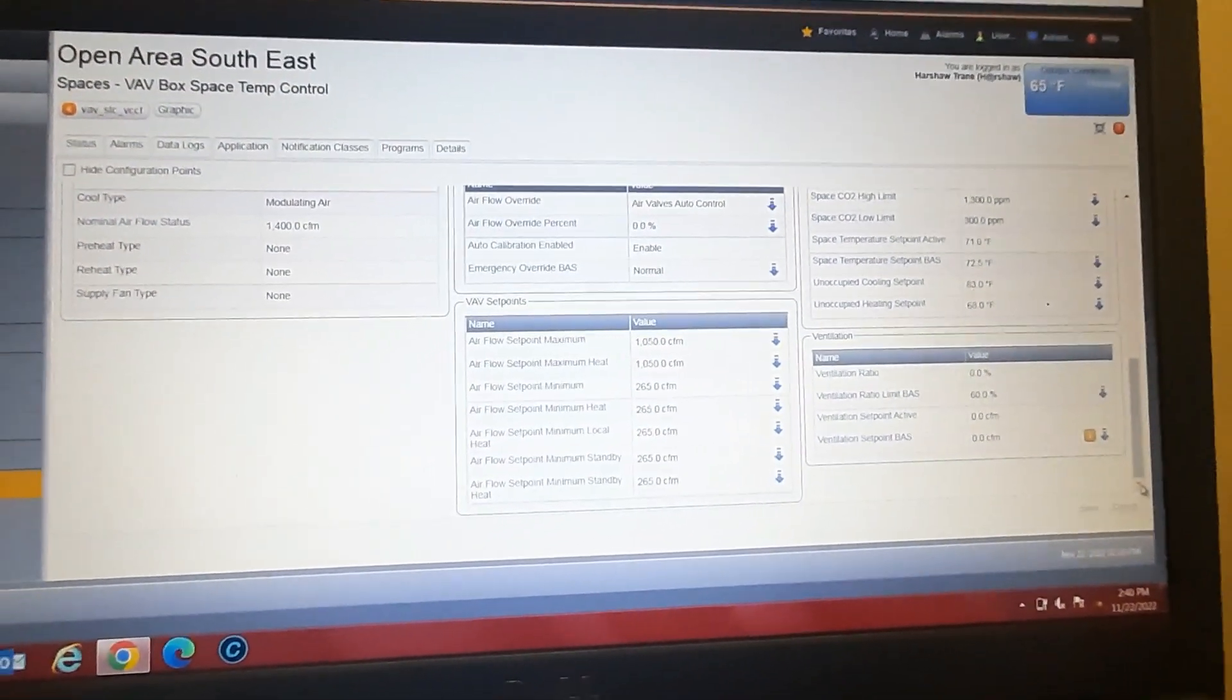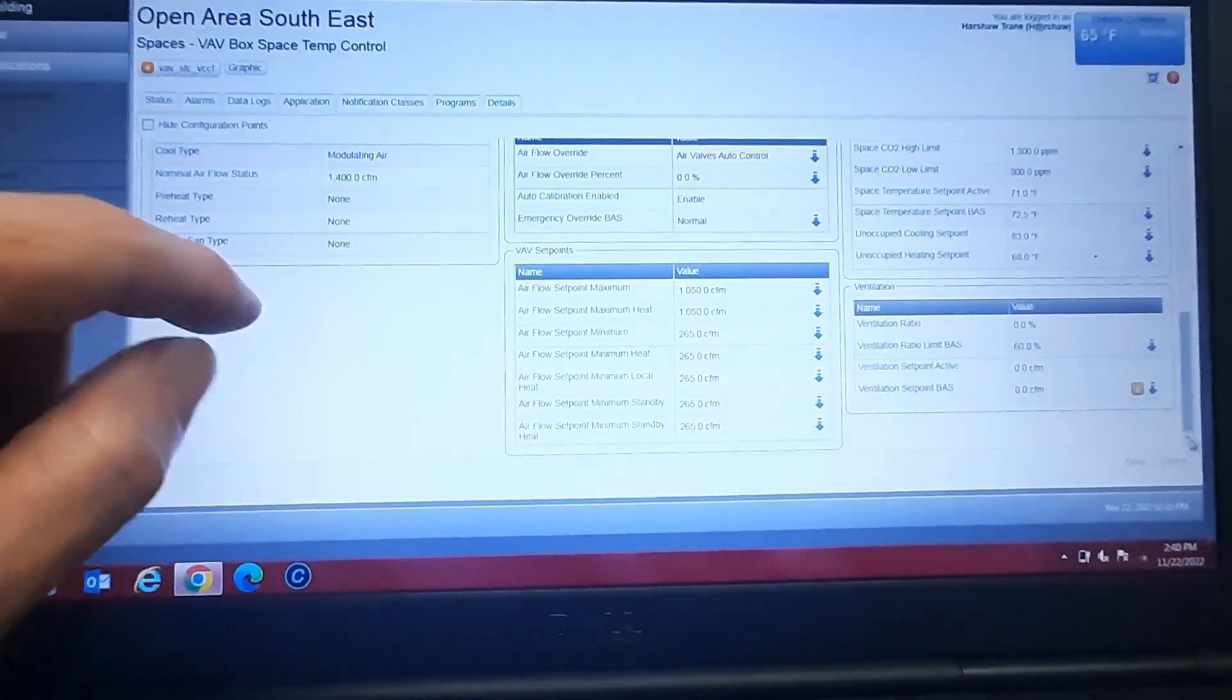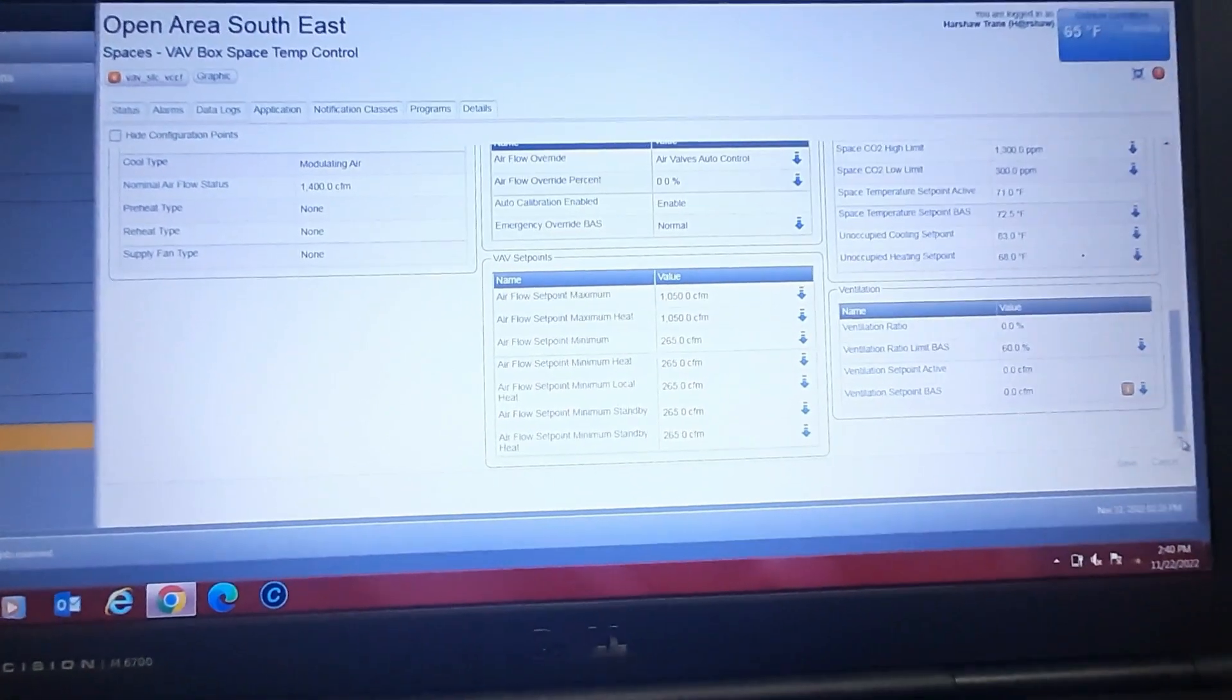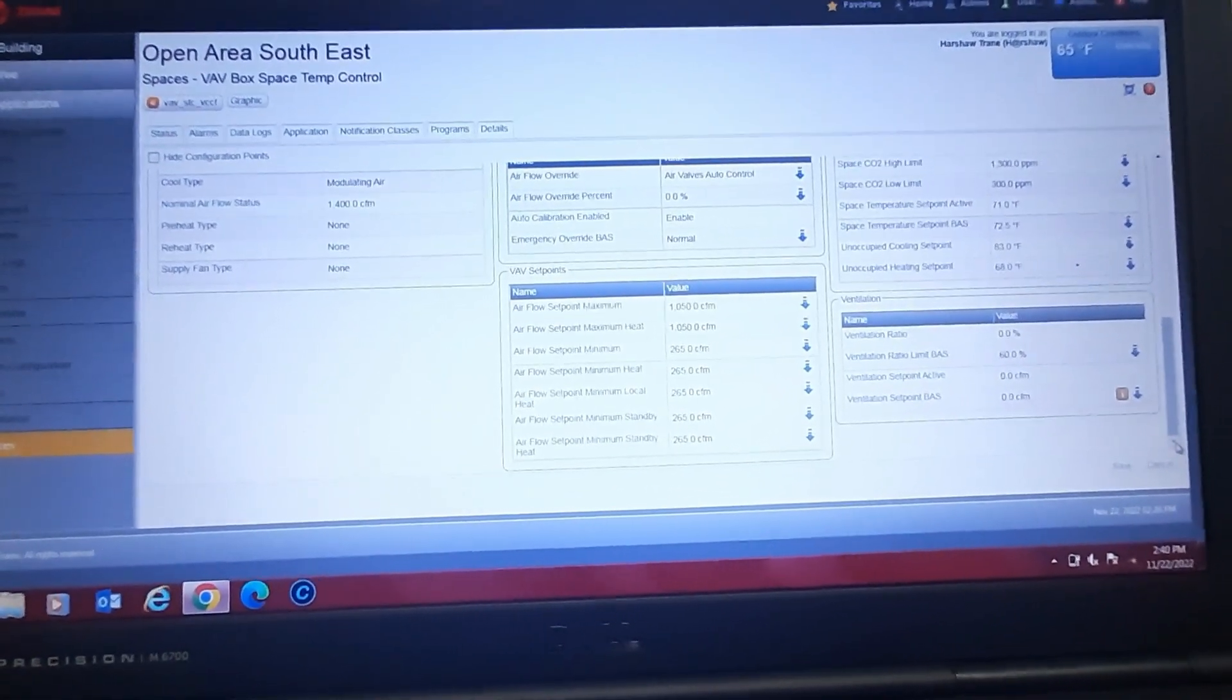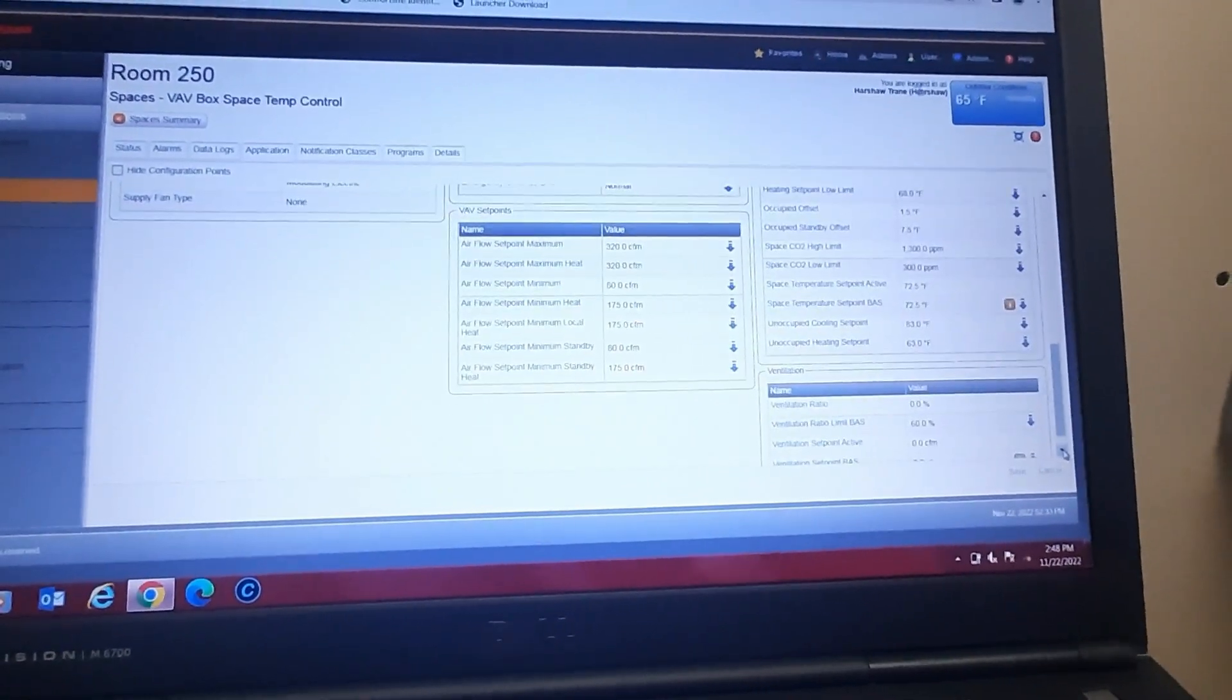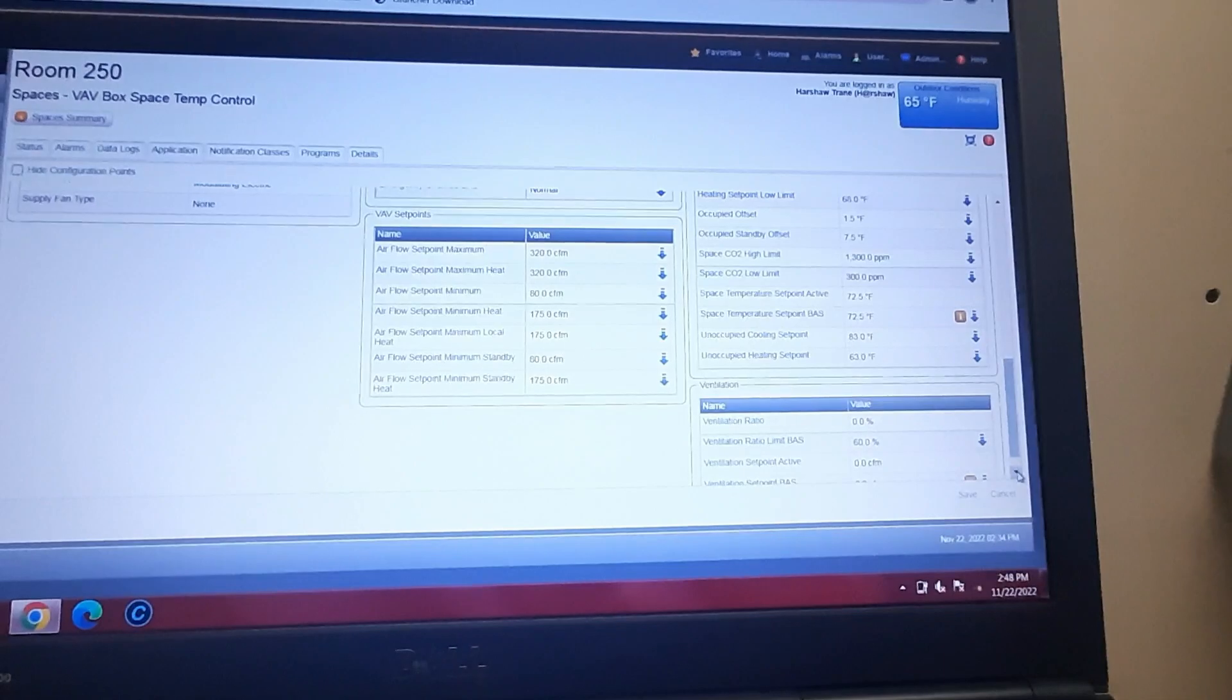So here's what I'm seeing. This is in the center of the building and you can see reheat type none, there's no reheat. So this is a straight VAV box, so we're going to set our minimum, at least the heating set point to zero, that way if it calls for heat it turns the damper off all together. Probably be some air leakage, but it's a big space. Even 200 CFM of moderate air is going to keep it cooler than necessary. Probably the exterior, on the other one, the other box is on the exterior, it's for offices, so it should have heat. We'll go in and look at that one in a second. So on this one we can see I do have modulating electric heat, so we don't want a zero set point because we need airflow for the electric heater. So I'm not going to adjust any of this. Looks like the minimum local heat 175 CFM, serves just a few offices, so I'm not going to mess the airflow on that one.